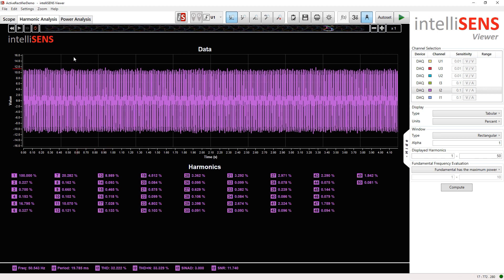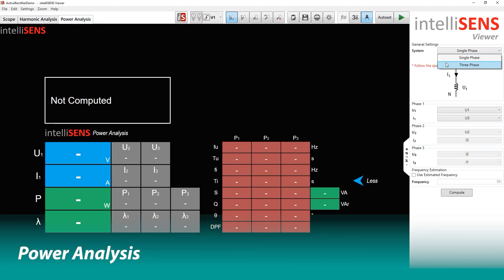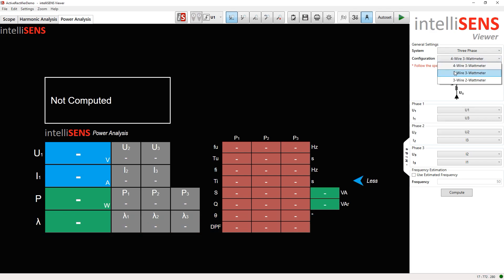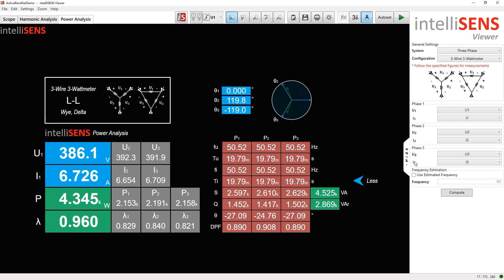Finally, we will perform power analysis to get the power factor along with the output power. We select a 3-phase system in a 3-wire, 3-wattmeter configuration. After pairing up appropriate voltages and currents, we can compute the power quality. Here, you can see the power factor is 0.96, which is quite good and easily satisfies our criteria.